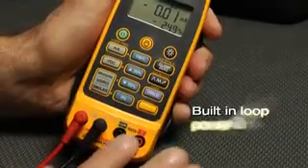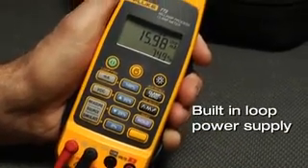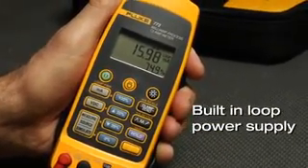In addition, the 773 has a built-in loop power supply, so you can power a transmitter and measure its milliamp output signal for testing and troubleshooting.